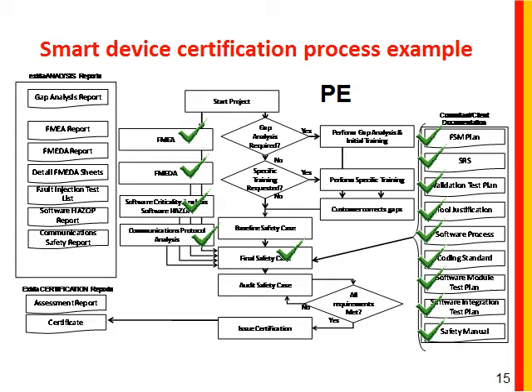All of this analysis is documented in an FMEDA report, a fault injection test, a detailed datasheet, software HAZOP reports, and communications reports. Finally, if all requirements are met, an independent auditor checks the safety case and issues a certificate and an assessment report, which we require to be publicly available documents. For the most part, certificates and the assessment report — which is an important part — are available on the exida website.